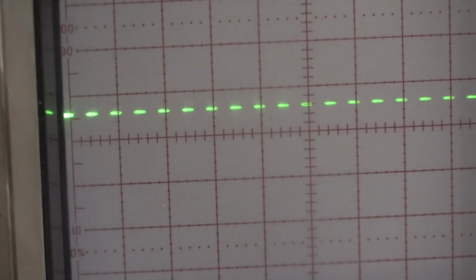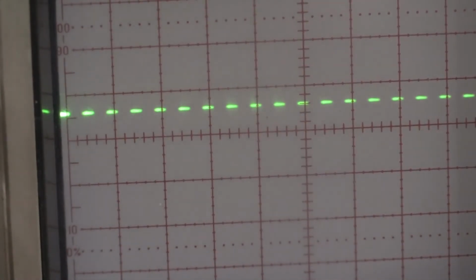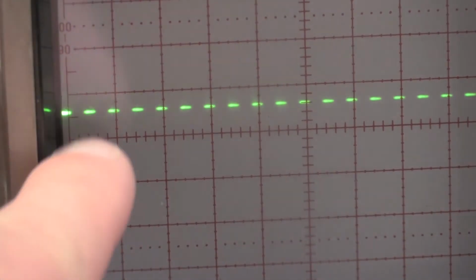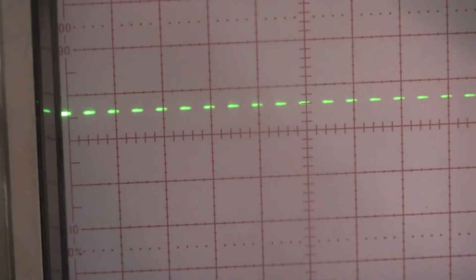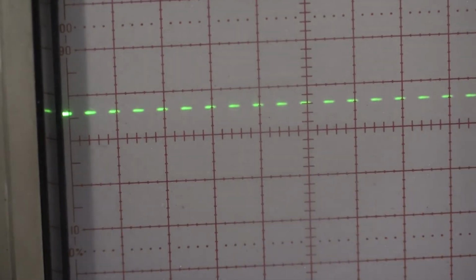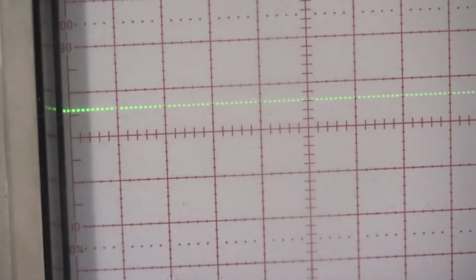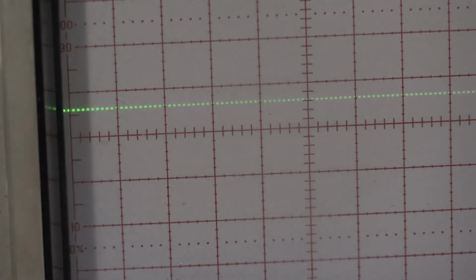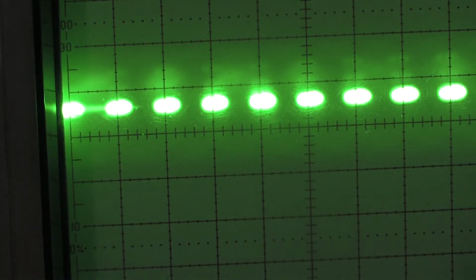Okay, checking the Z-axis modulation, I have a 200 millivolt signal going into the front end of the scope at 20 megahertz, and we do see Z-axis modulation. External trigger as requested. I also need to check now, let's see, 0.5 microseconds, and we need to go to 2 volts peak to peak and 2 megahertz. I'm using my RF signal generator because it'll do it. This is pushing the output a lot, but amplitude 1 volt, frequency 2 megahertz. And we also have amplitude modulation, and wow, that is bright. I'm not going to let that go for too long.